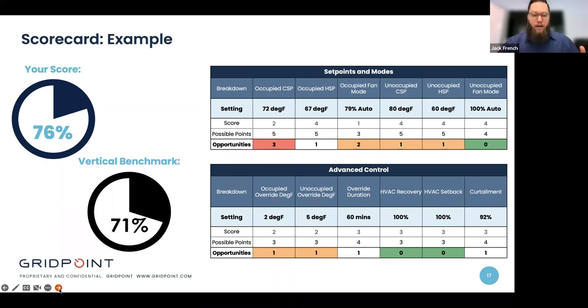If we have to adjust cooling set points in certain zones because of comfort issues, are there other zones that we can adjust so that we don't change our score, or so that our score maybe even improves? If we have to make a sacrifice in one zone, can we make up for that with another zone? And can we maintain the score that we want? If we start out at 76 and that's where we want to stay, then we shouldn't see that score lower. So if there are changes that need to be made, we need to look for other opportunities to make that change back up, because that's going to lead to, like we've said, unnecessary energy expenditure, increase in HVAC runtime, and potentially premature failure of the units.